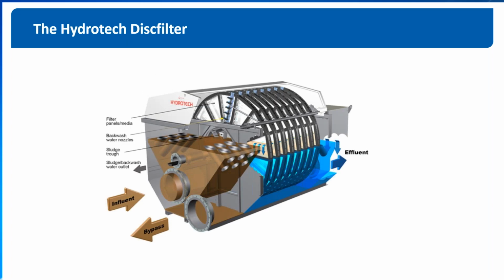So this is an image of a Hydrotech disc filter. This is an inside-out technology where the water flows into a drum. The water passes through a disc and out through a filter panel, which is mounted on the disc. The clean water will be sitting inside a tank before passing over an outfall weir, and that clean water is used in a backwash process.